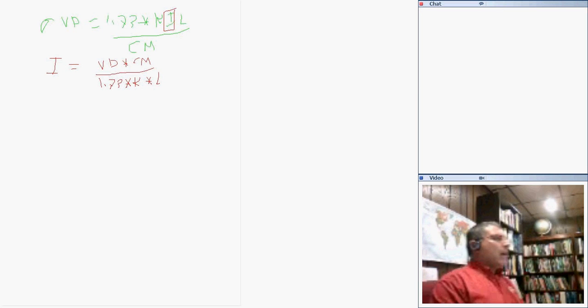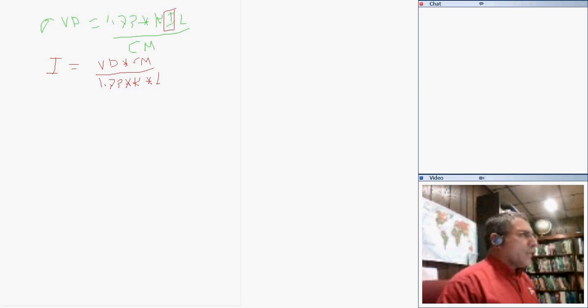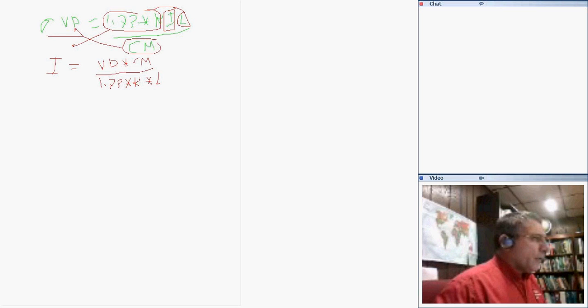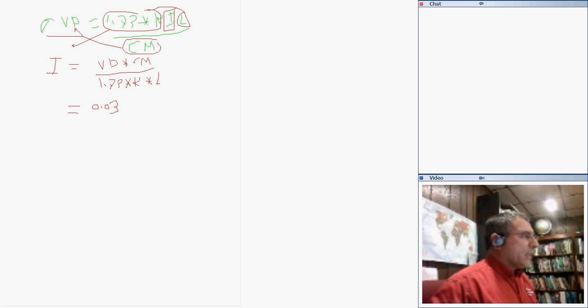K, and the length. You flip the formula to solve for I: what's at the bottom with I goes on the top on the other side of the equation, and what's on the top with I goes to the bottom. The voltage drop approved by the code for feeders is 3%, so 3% by code recommendation means 0.03. Multiply by the voltage, 480, then multiply by the circular mil.